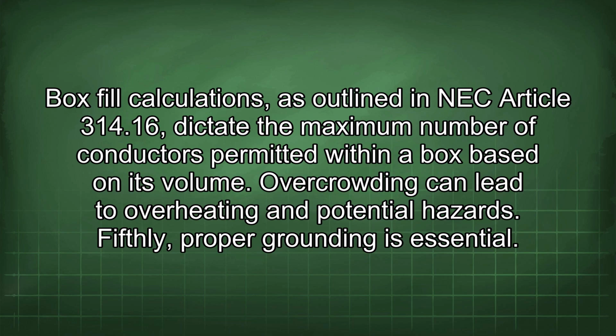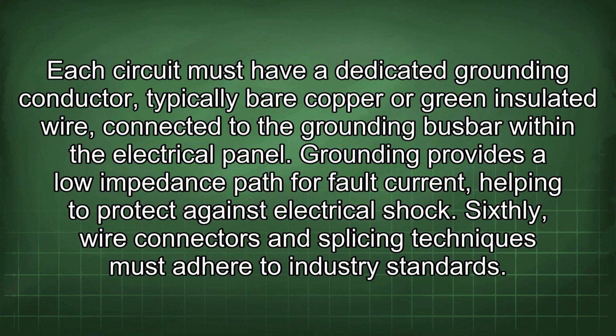Fifthly, proper grounding is essential. Each circuit must have a dedicated grounding conductor, typically bare copper or green insulated wire, connected to the grounding busbar within the electrical panel. Grounding provides a low impedance path for fault current, helping to protect against electrical shock.